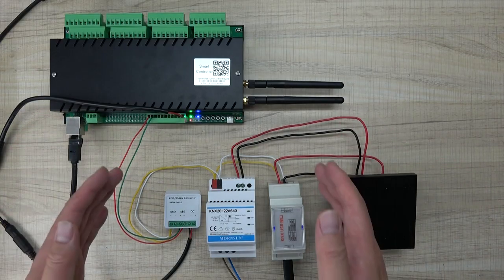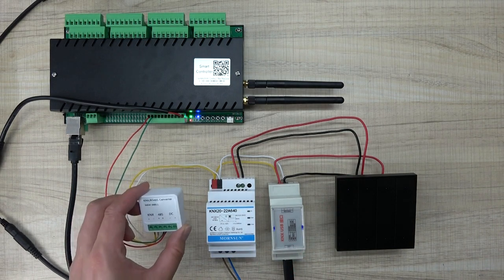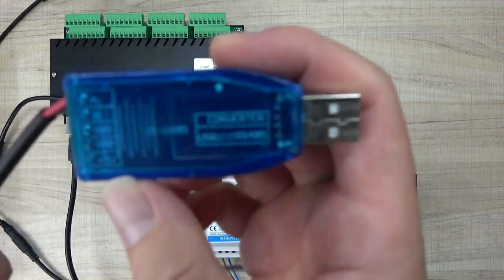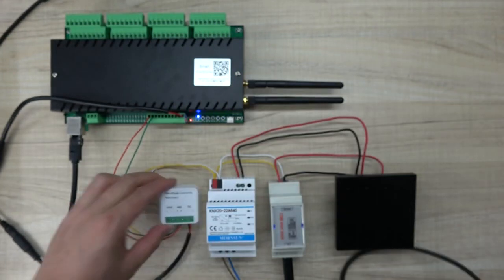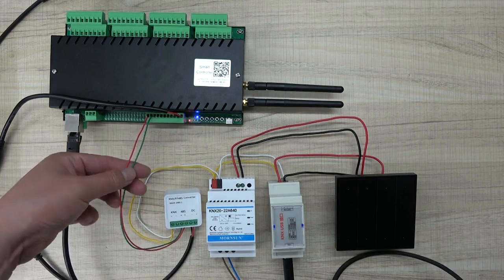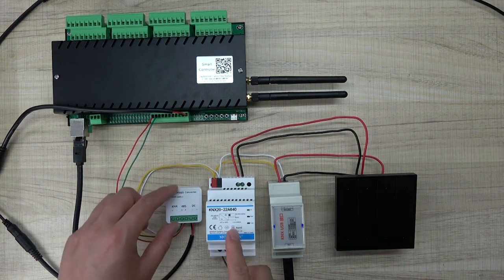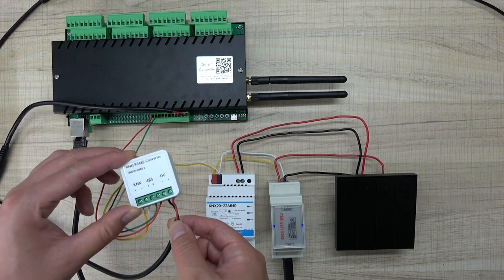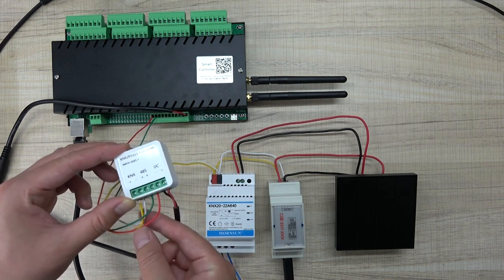Now I will show you step by step how to use this converter and how to configure the PC software. First, we should use the USB to RS485 adapter. You can see that converter RS485 A and B. I will connect to this A and B firstly. I just disconnect these two cables A and B from the H32B Pro. Power off the system first. This converter will need a 12V or 24V power supply, and also needs to connect with the RS485 and KNX bus.